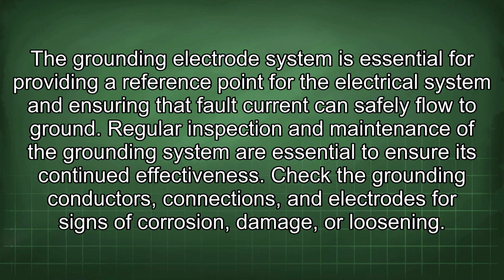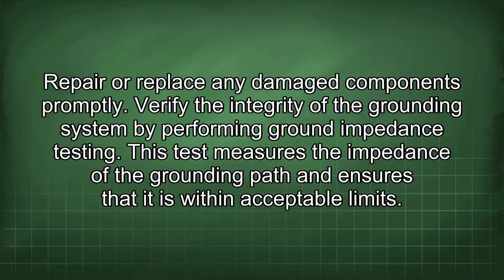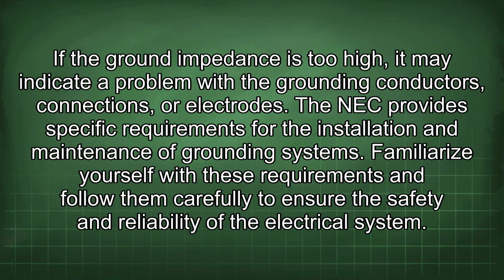Check the grounding conductors, connections, and electrodes for signs of corrosion, damage, or loosening. Repair or replace any damaged components promptly. Verify the integrity of the grounding system by performing ground impedance testing. This test measures the impedance of the grounding path and ensures that it is within acceptable limits. If the ground impedance is too high, it may indicate a problem with the grounding conductors, connections, or electrodes.